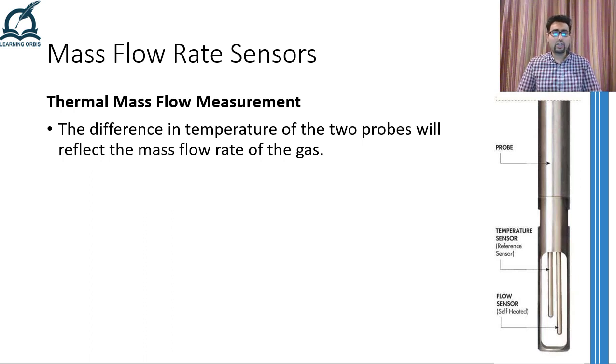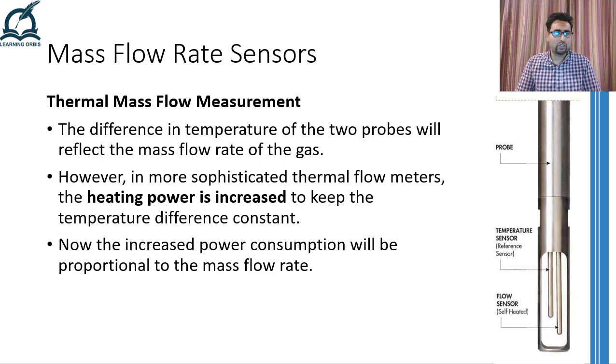At this point, there are two versions of this mass flow rate sensor. In the first one, the temperature difference between the two probes will be directly proportional to the mass flow rate of the fluid. Whereas in the second version, additional power is supplied to the heater present in the flow sensor probe so that the difference between the reference and the flow sensor probe is tried to maintain. In this version, the power required by the heater to maintain the temperature difference will be directly proportional to the mass flow rate of the fluid.